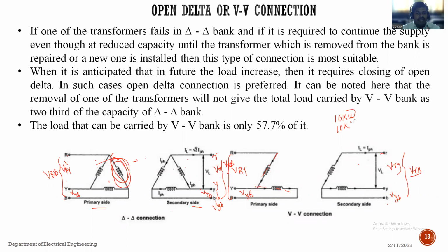If any one transformer in a three phase bank is taken out of service, damaged, or open circuited, the remaining two transformers will carry a load, but less load compared to the three phase bank - around 57.7% of load.